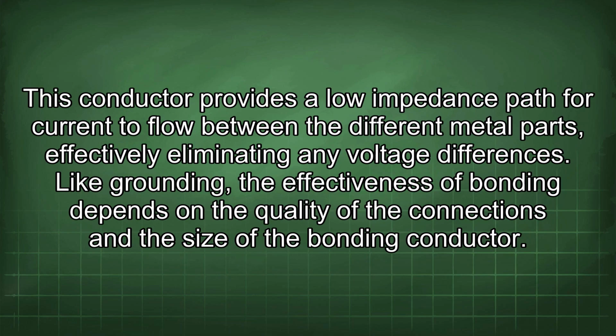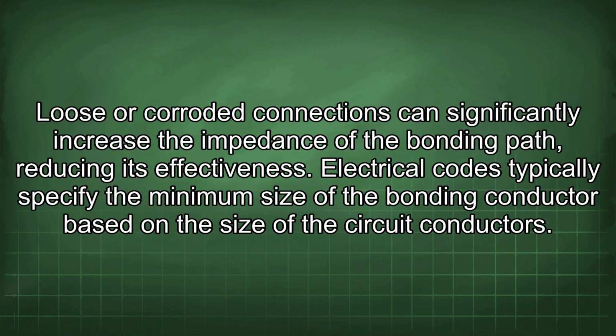This conductor provides a low impedance path for current to flow between the different metal parts, effectively eliminating any voltage differences. Like grounding, the effectiveness of bonding depends on the quality of the connections and the size of the bonding conductor. Loose or corroded connections can significantly increase the impedance of the bonding path, reducing its effectiveness. Electrical codes typically specify the minimum size of the bonding conductor based on the size of the circuit conductors.